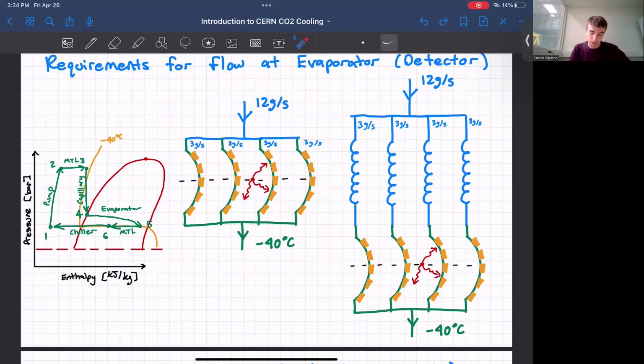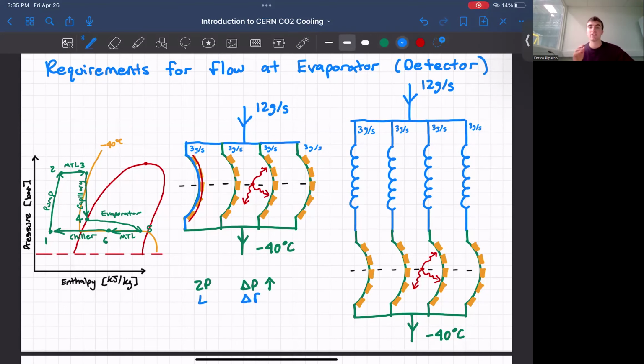In this first diagram, we have no capillaries, and we're having 12 grams per second of refrigerant. If the evaporators are calibrated, then we have the same flow rate across all evaporators. However, if an evaporator's silicon sensors break, then there is no longer heat transferred from the silicon sensors to the evaporator. As a result, the refrigerant will no longer boil and will remain liquid. Now, in two-phase, the pressure drop at the same mass flow rate is much higher than in liquid. This is because at the same mass flow rate, two-phase is flowing at higher flow speeds, and as a result has higher frictional pressure drops.